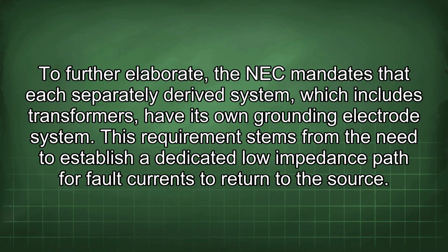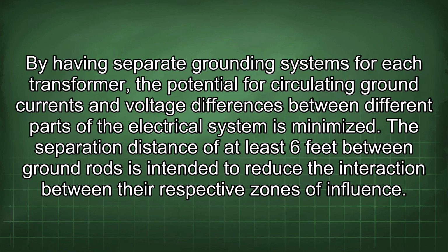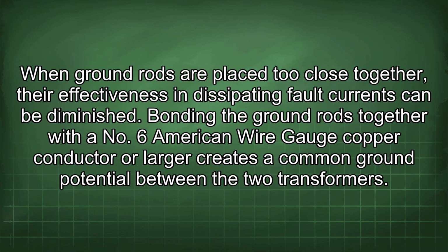To further elaborate, the NEC mandates that each separately derived system, which includes transformers, have its own grounding electrode system. This requirement stems from the need to establish a dedicated low-impedance path for fault currents to return to the source. By having separate grounding systems for each transformer, the potential for circulating ground currents and voltage differences between different parts of the electrical system is minimized. The separation distance of at least 6 feet between ground rods is intended to reduce the interaction between their respective zones of influence. When ground rods are placed too close together, their effectiveness in dissipating fault currents can be diminished.